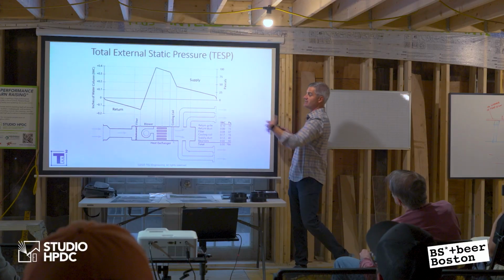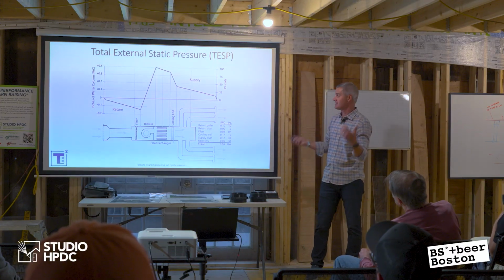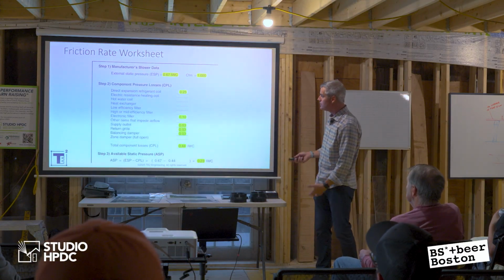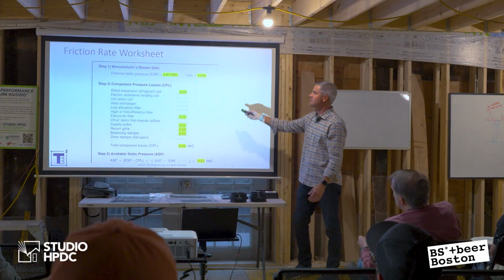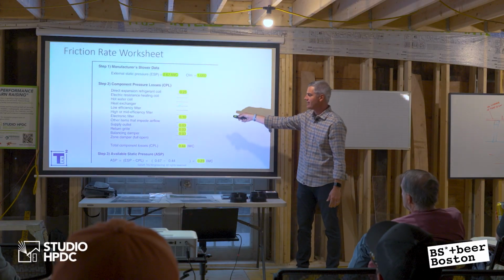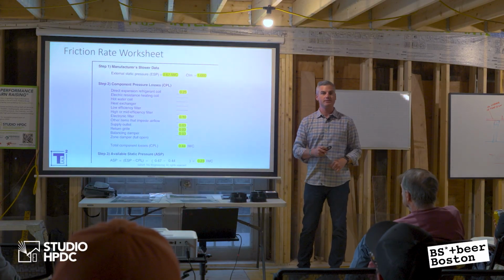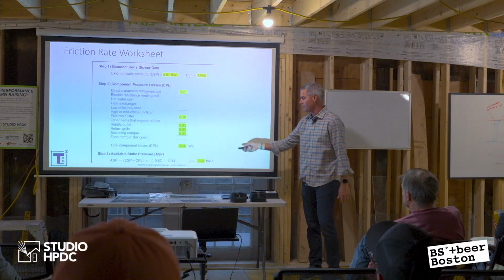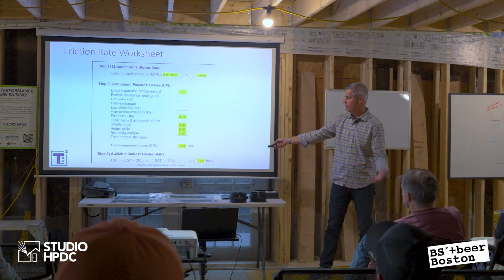So all of this stuff, it's a system. You've got to treat the whole HVAC system as a system. It's all interrelational. I'm not going to go through the whole chart, but basically it says, what's my blower do? And then I subtract out all of my resistances, and I get a magic number in terms of inches of water column, in this case, 0.23 inches of water column.